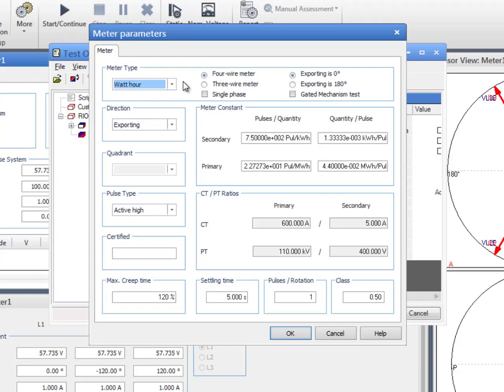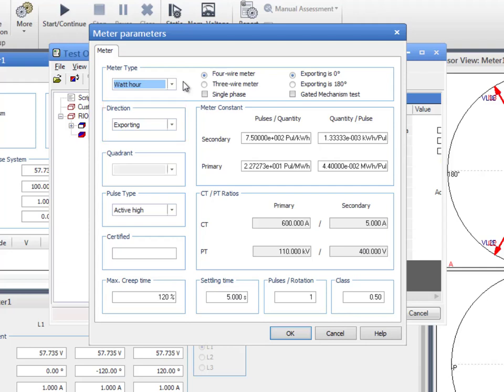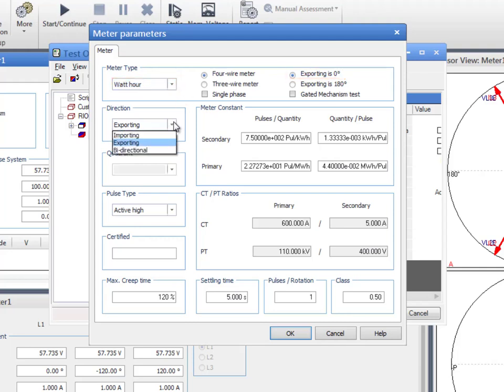Depending on the power flow definition, we have to indicate whether exporting should be considered from the point of view of the generator, that is, 0 degrees, or from the point of view of the consumer, that is, 180 degrees. Set this parameter according to the meter's configuration. When choosing one of the meter functions, it is necessary to specify the energy direction of the test. In our particular case, we will check the energy in watt-hours from the generator's point of view. We can choose from importing, exporting, or bi-directional. We will choose exporting, so the power angle will be set to 0 degrees by default.